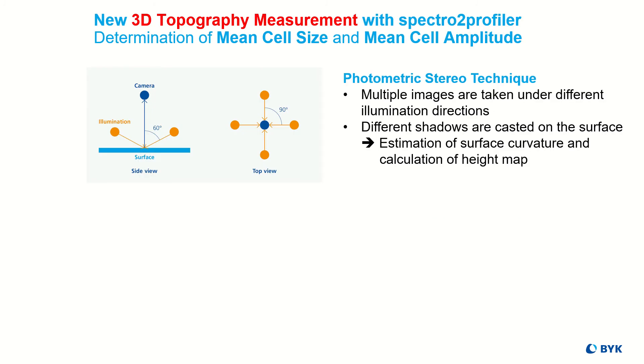To measure 3D topography, the instrument takes multiple images under different illumination directions. Different shadows are cast on the surface, which allows estimation of surface curvature and calculation of a height map.